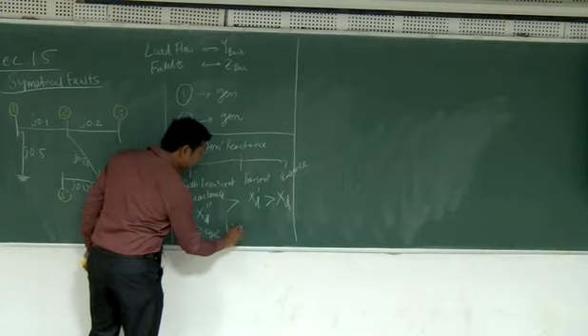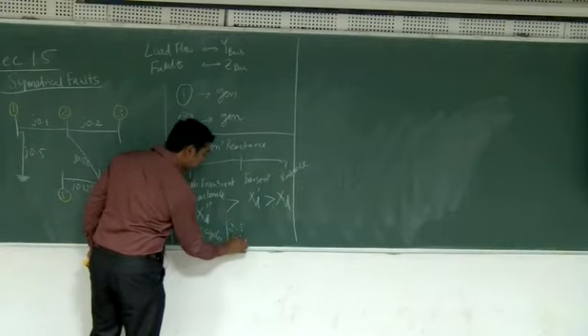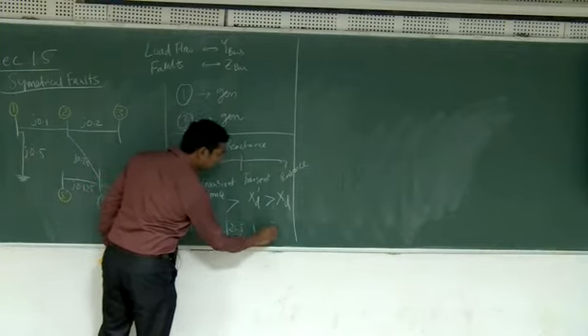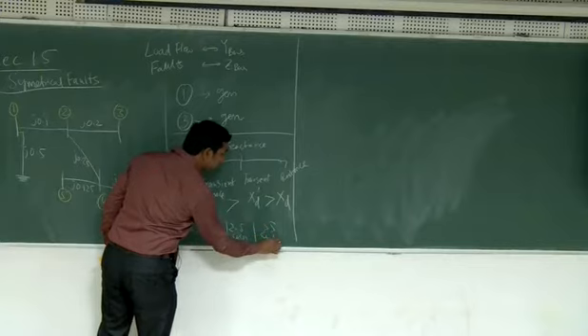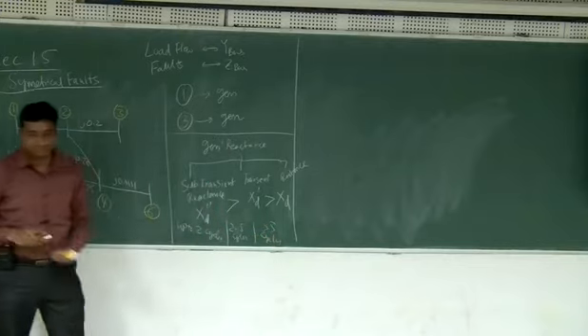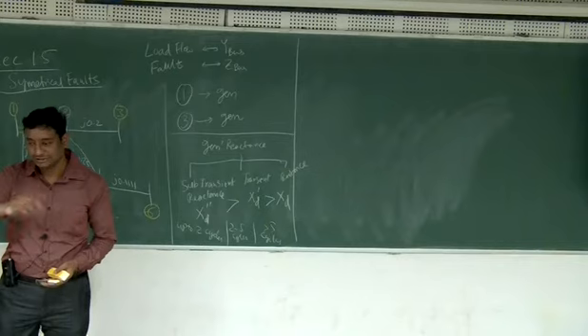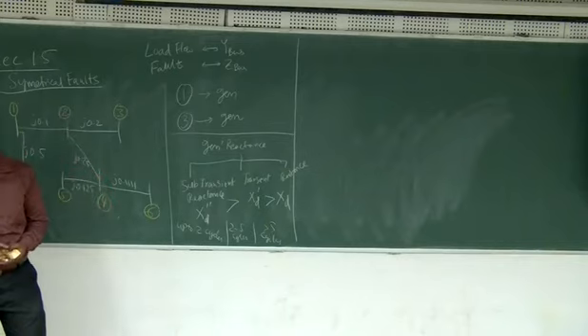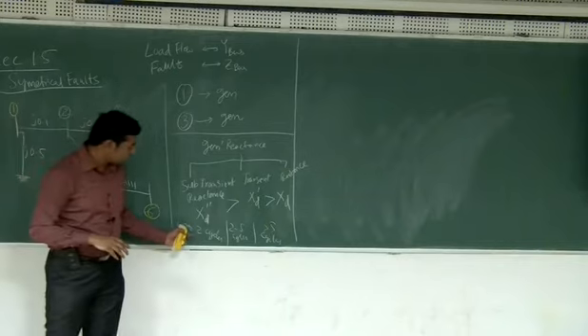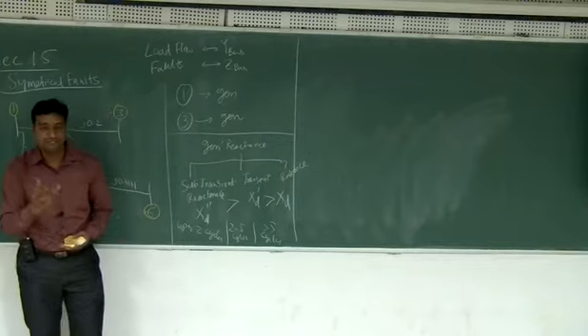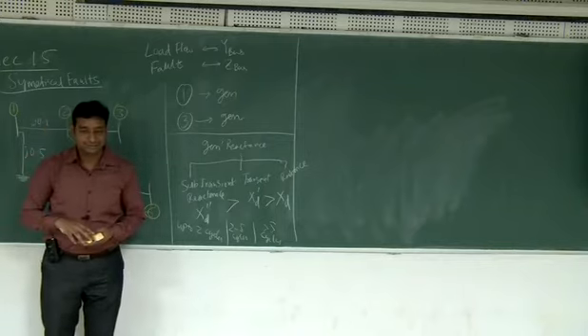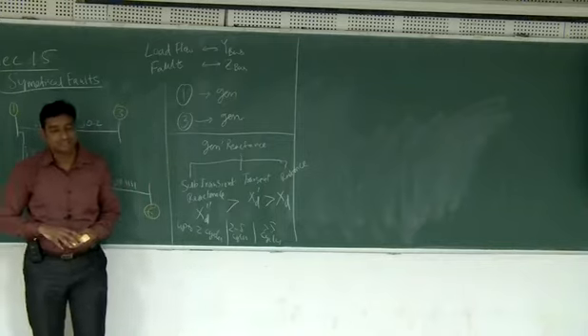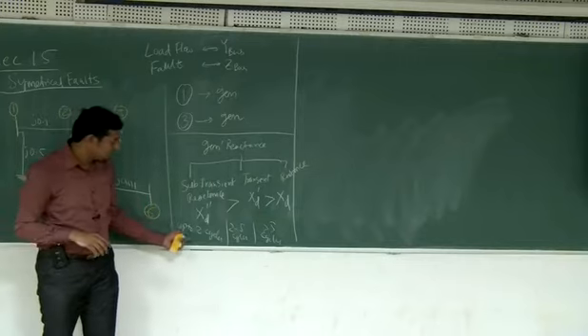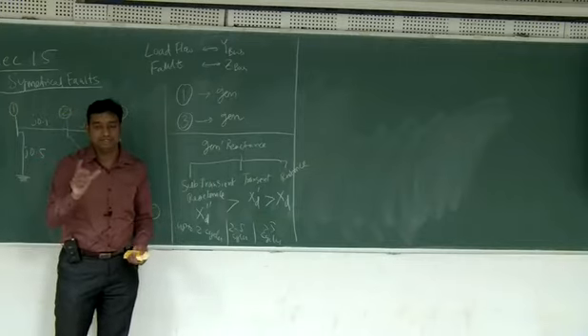This is maybe 2 to 5 cycles, and then this is more than 5 cycles. So when I say cycle, what does that mean? It is a time period of your AC waveform. Okay. So if you have a waveform of 50 hertz, the time period will be how much? 1 by 50, that is 20 milliseconds. So 2 cycles means 20 plus 20, 40 milliseconds.